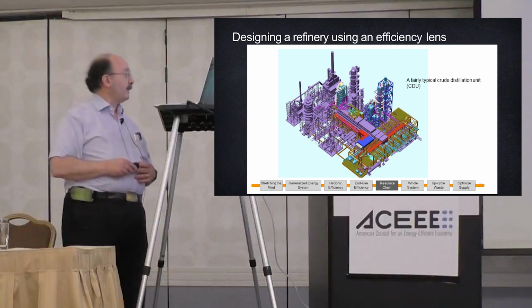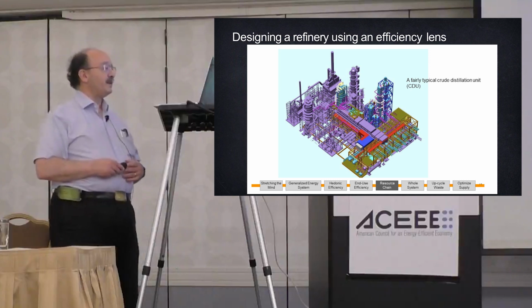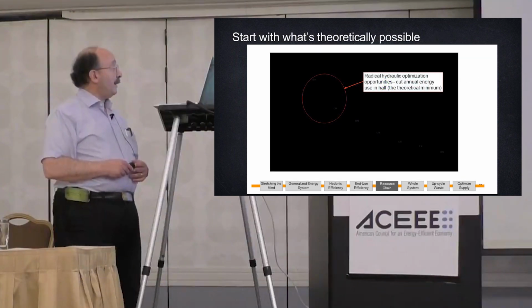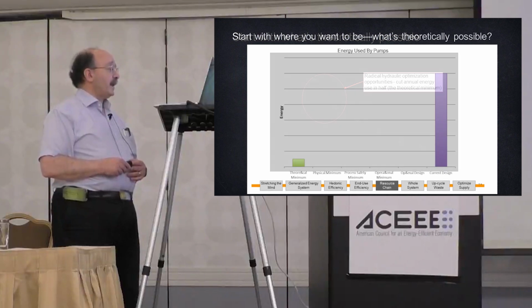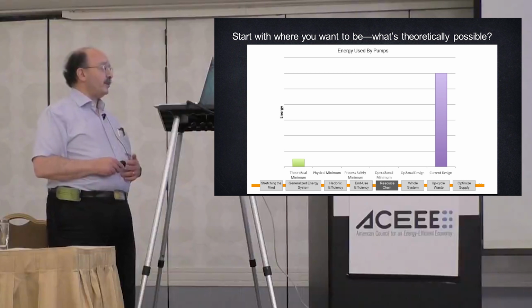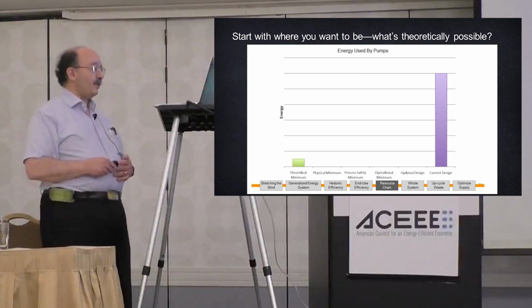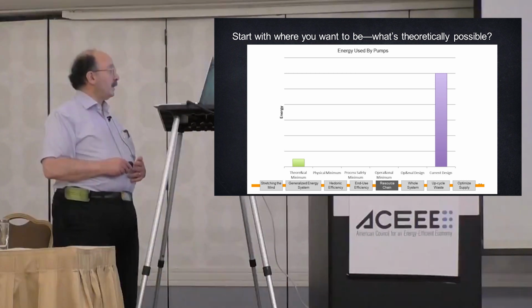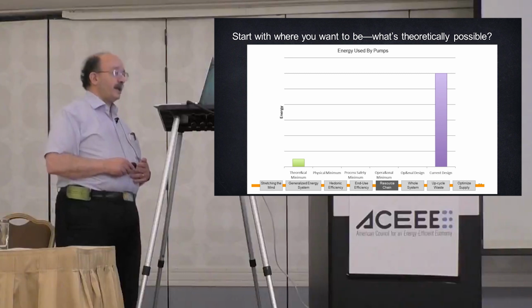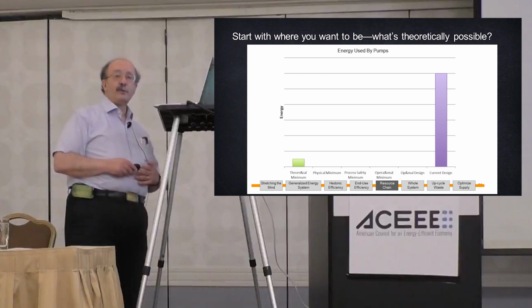So we asked where the pumping energy goes, and we found some fat opportunities to wring out a lot of it, particularly as I've just described. A standard nominal design would use about 12 times the theoretical minimum pumping energy, so we started redlining the standard design and finding a lot of opportunities to untangle the pipe noodles.